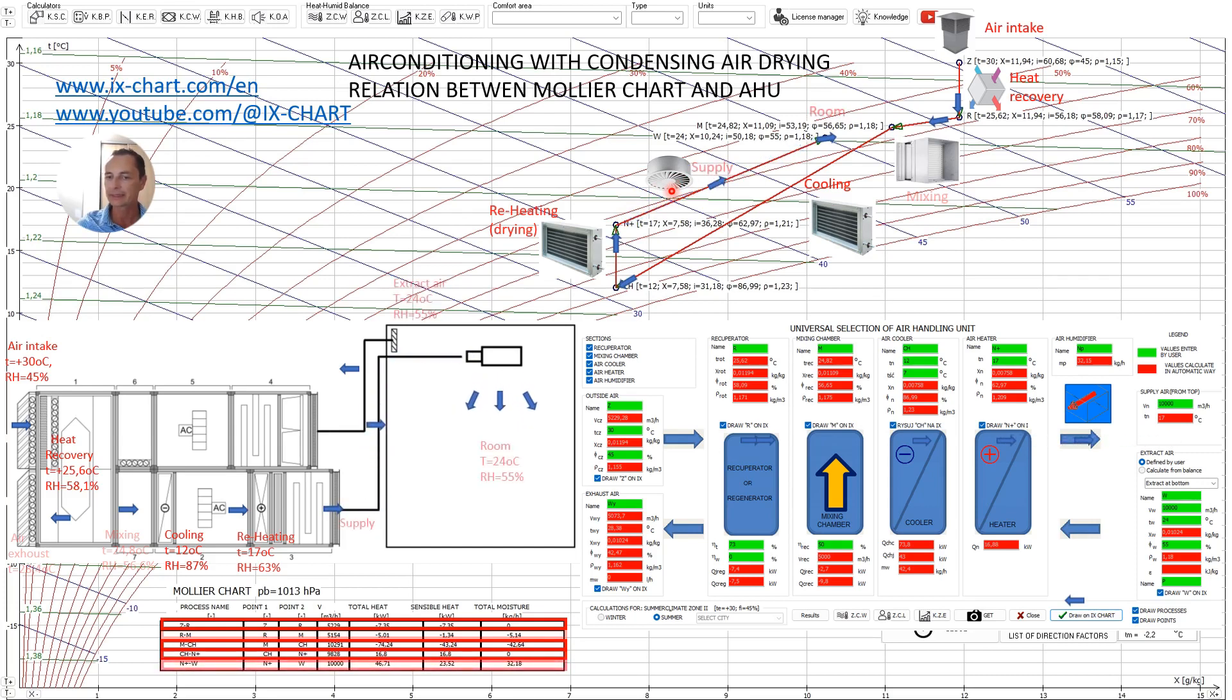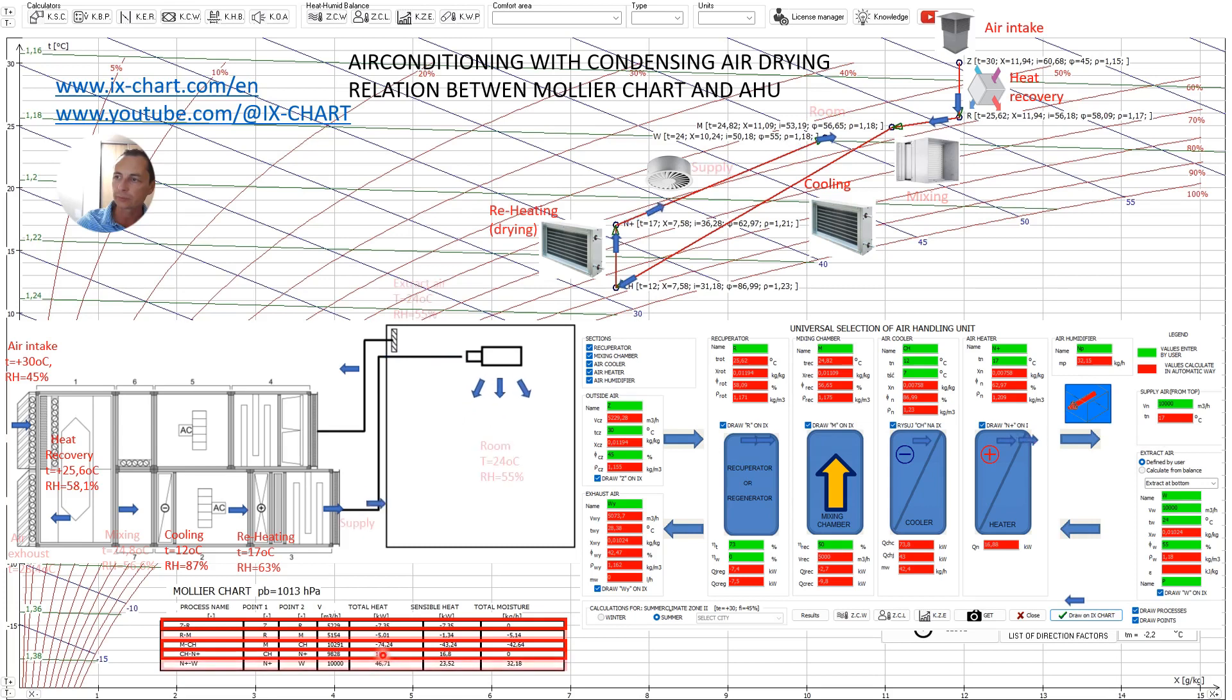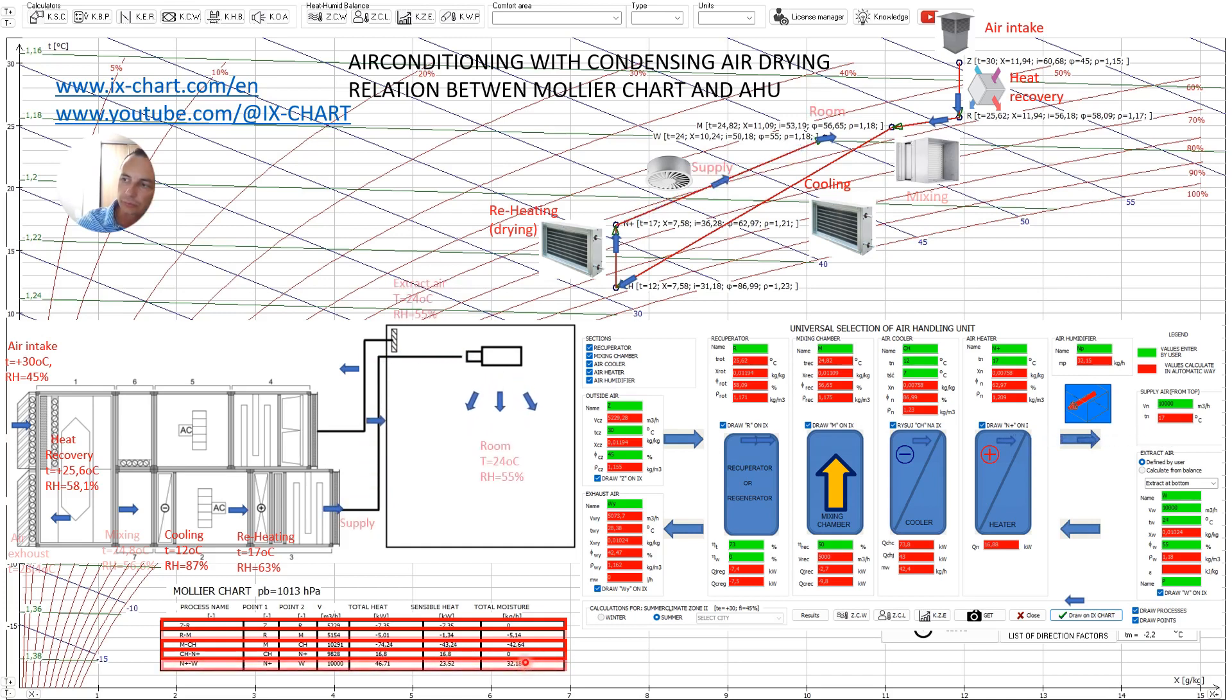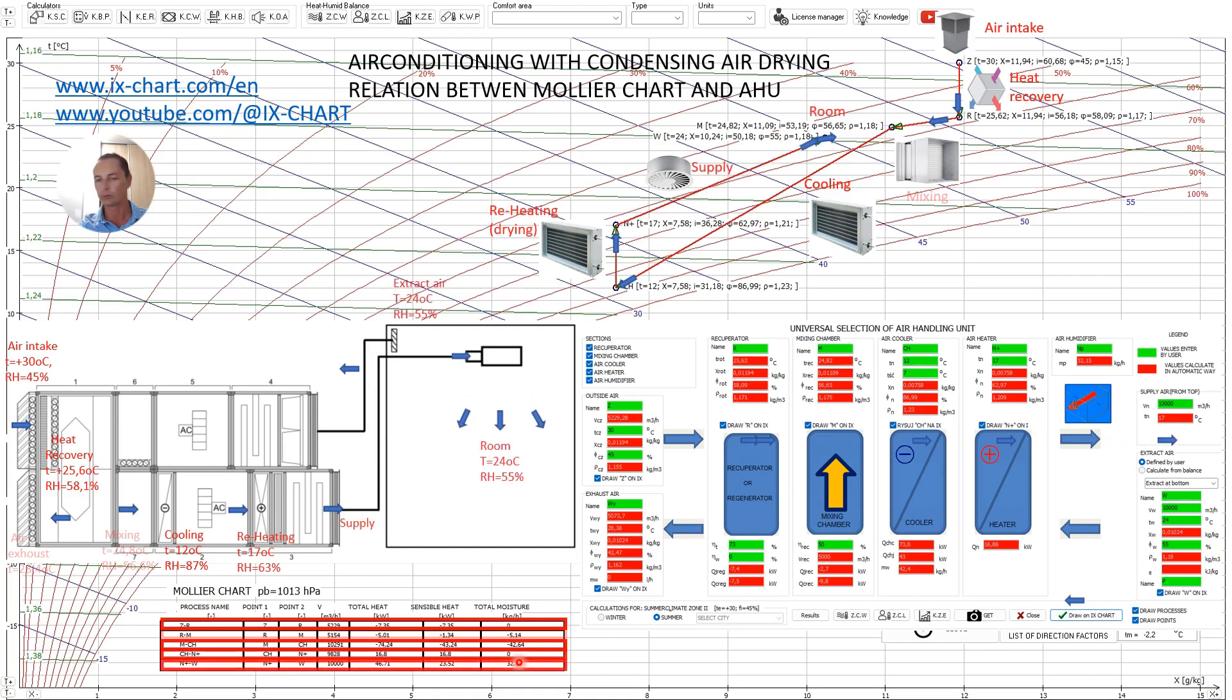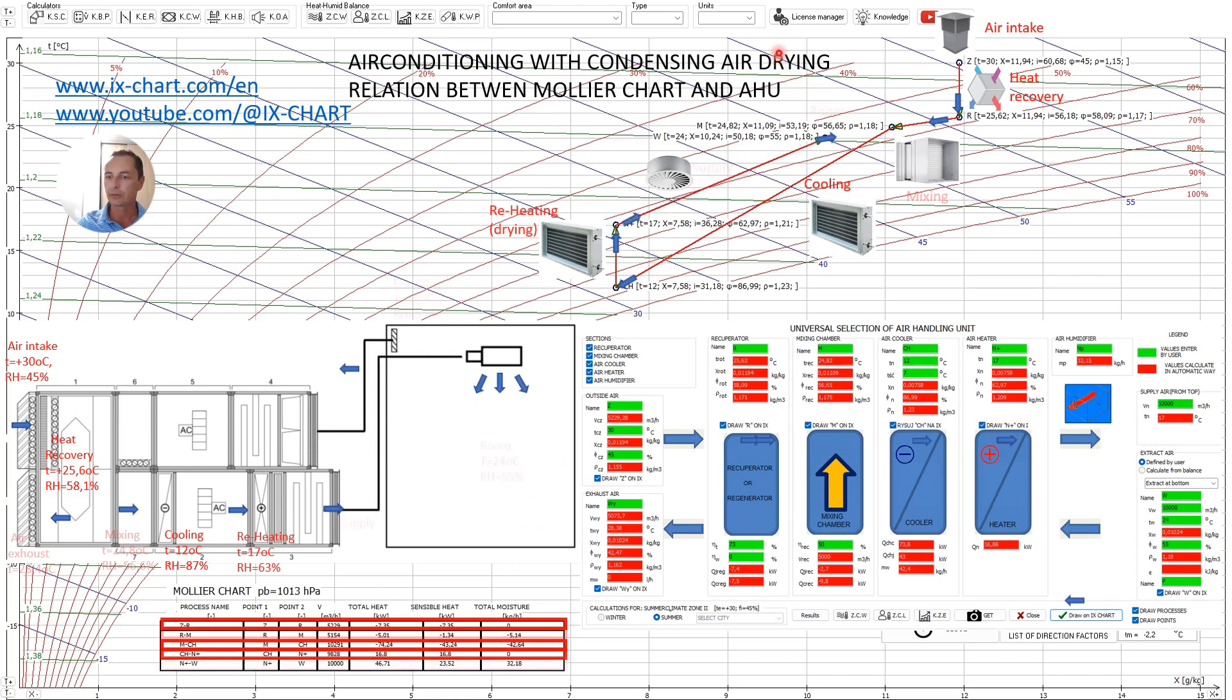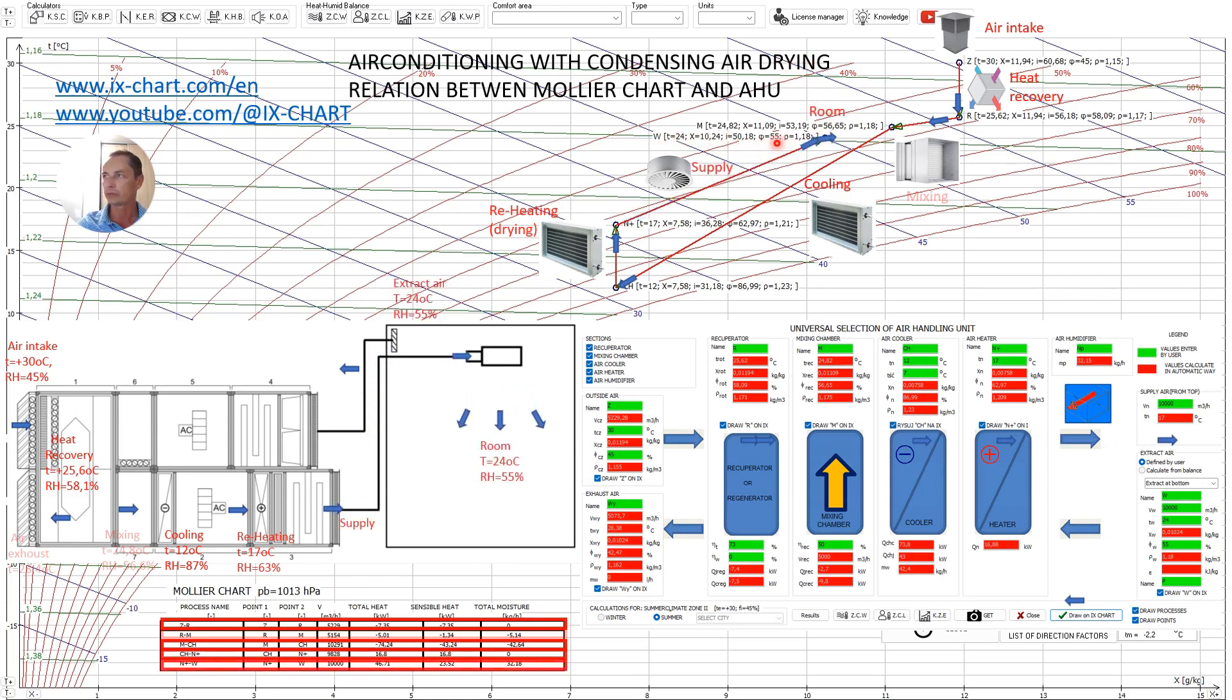In this case we removed from this room 46.7 kilowatts total heat, 23.5 kilowatt sensible heat and 32.2 kilograms of moisture. And as you can see in this way we achieved our required parameters in the room 24 Celsius degrees and 55 percent of relative humidity.